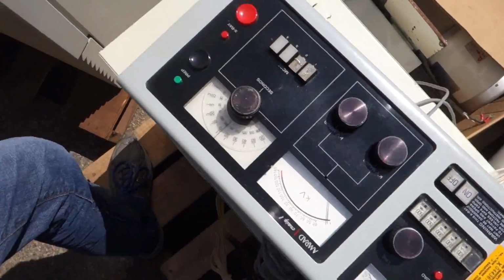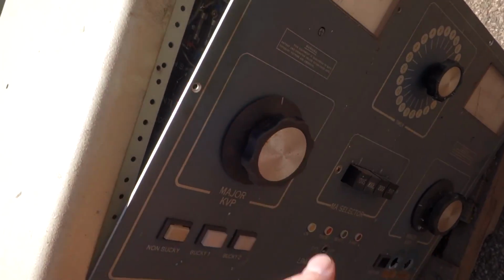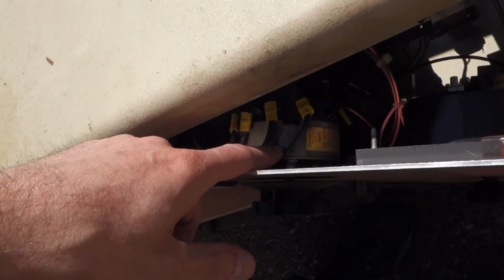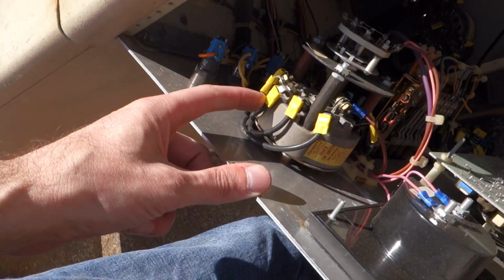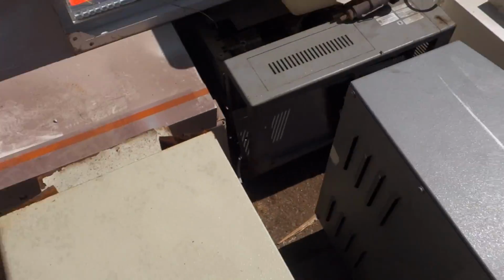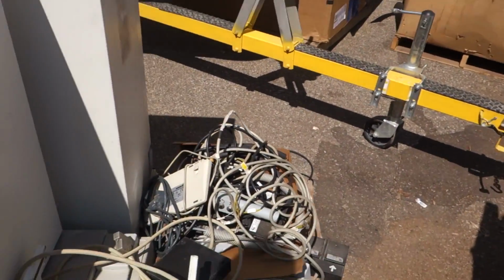and I understand. On all of these boxes, there are 2 big knobs, right here. Big knobs, right? And you look inside, that's a big switch. And these big switches tend to go down to an inductive current limiter. They gutted the one out of there. Let's find an inductive current limiter. Oh, I had a good example of one.